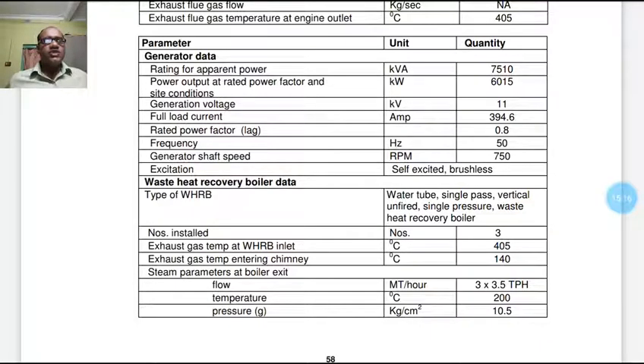Type of waste heat recovery boiler: water tube, single pass, vertical, unfired, single pressure waste heat recovery boiler. Number installed here is 3. Exhaust gas temperature at boiler inlet is 405 degree centigrade. Exhaust gas temperature entering chimney is 140 degree centigrade. Steam at boiler exit is 3 into 3.5 TPH, temperature 200 degree centigrade, pressure 10.5 bar.